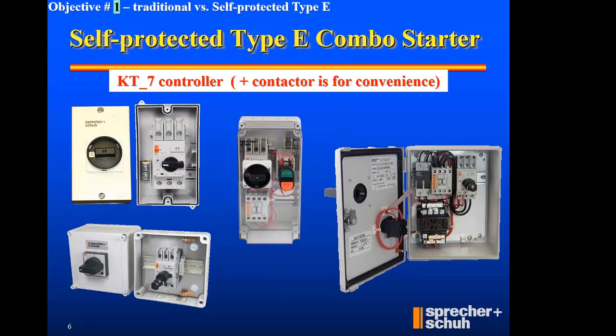And what I'm saying is, hey, that contactor added onto the bottom is merely for convenience of sending a remote signal. So that's what the contactor is for. Okay, so there we've got a nice economical quick starter, combo starter here that aligns it this way. And then as we get into the Hoffman hinged enclosure, industry standard kinds of stuff, no longer are we vertically aligning this stuff.